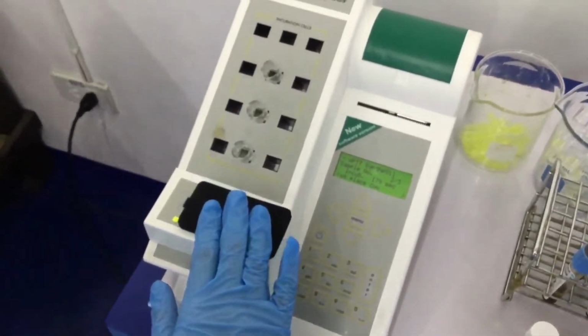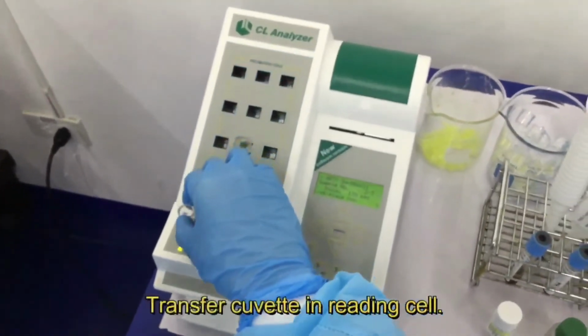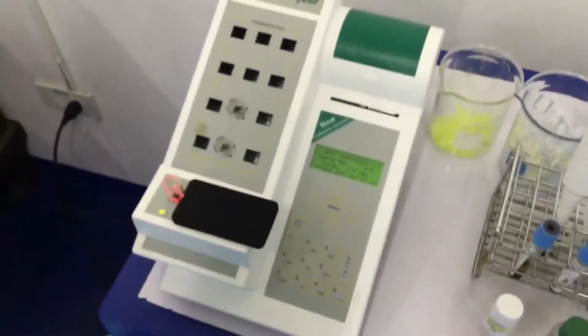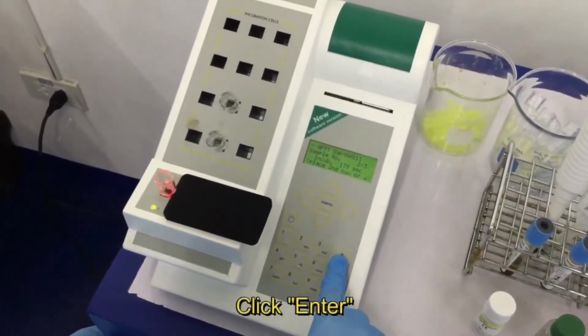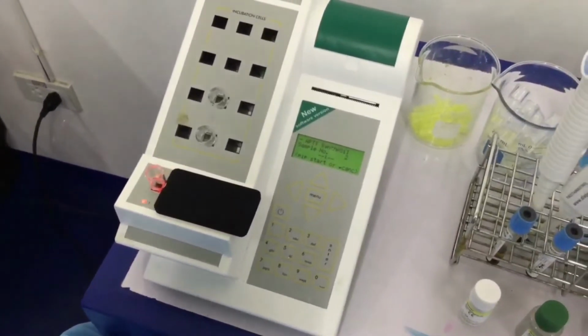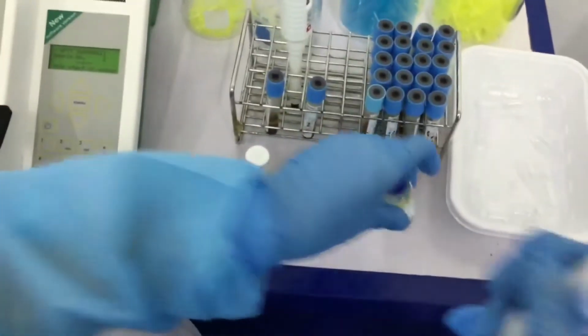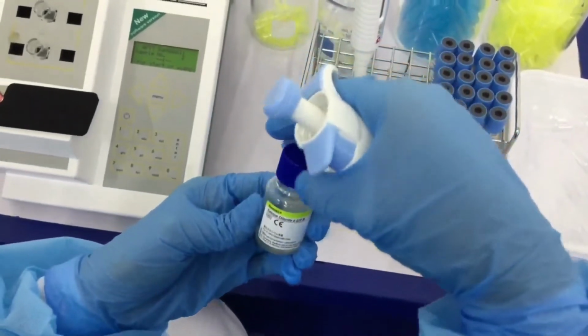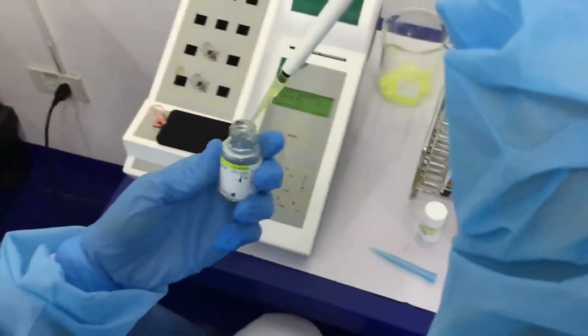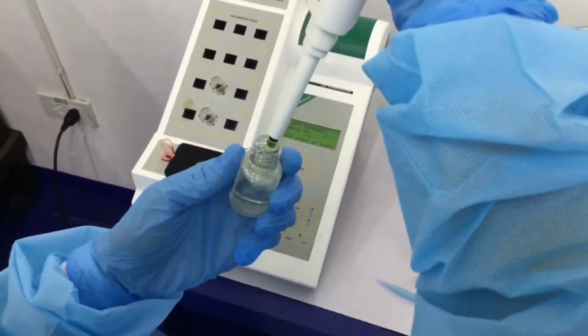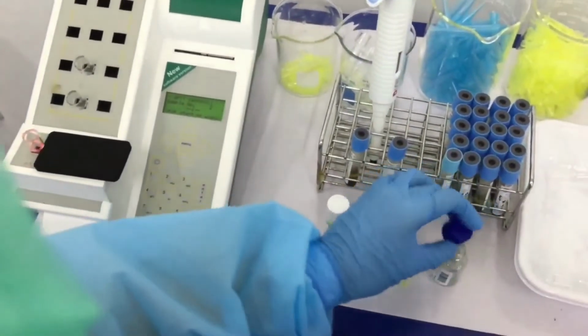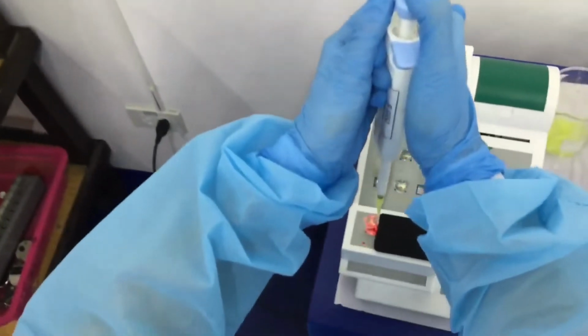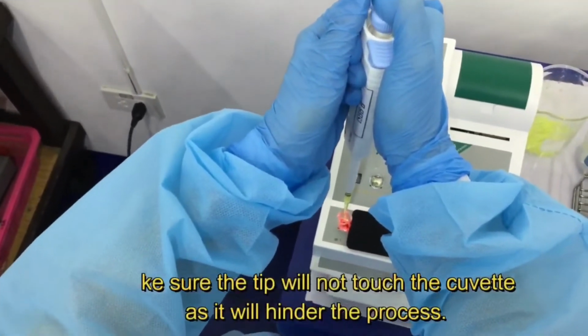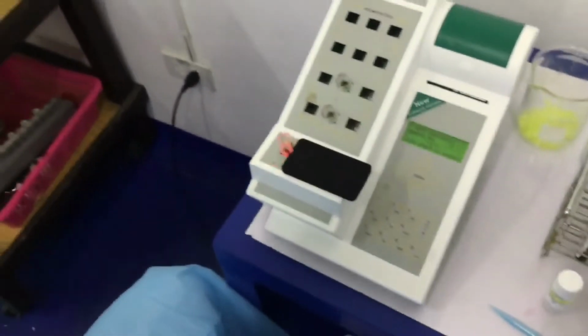Now transfer the cuvette and place it in the reading cell. Then click Enter. Now add 100 microliters of the blue cap reagent or the calcium chloride. Make sure that the tip will not touch the cuvette to avoid interferences.